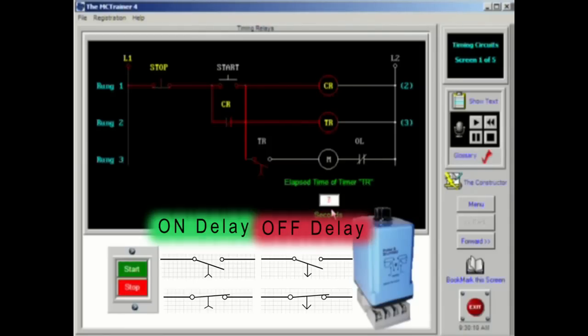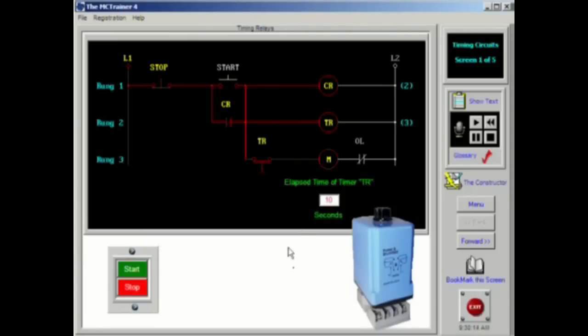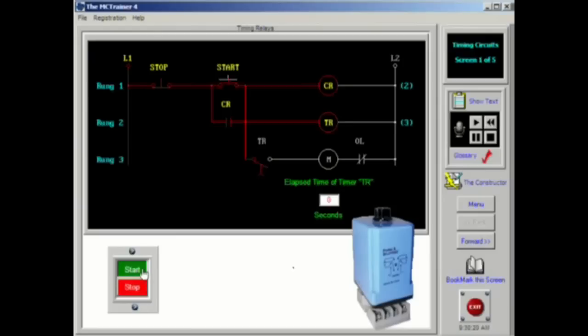They are on delay logic and off delay logic. The on delay is designed to activate its contacts after a preset time has elapsed. The timer coil must be energized to begin the timing period.